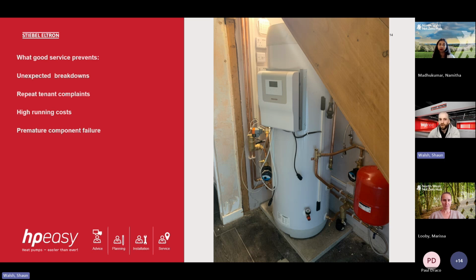Now, if one of our diverter valves failed, for example, rather than pulling the heat out of the buffer, we would then pull it out of the hot water tank, and then it would go to the heat pump. So then our hot water tank gets cold. So then the heat pump has to kick in and recover that energy. But once it's doing that in the winter, we then have to defrost it again. So we pull the tank temperature back down, and then you get stuck in a cycle of pulling the energy from the wrong places. So when we do the servicing, it's important that we check all the components are doing what they're intended to do, and that the heat and the energy is going where it's intended as well.